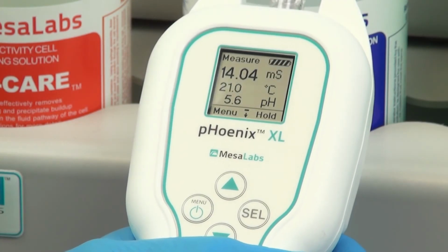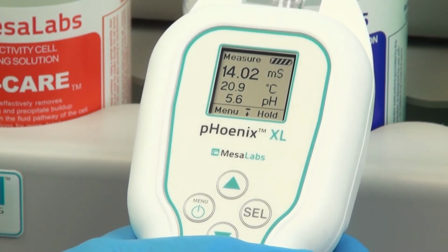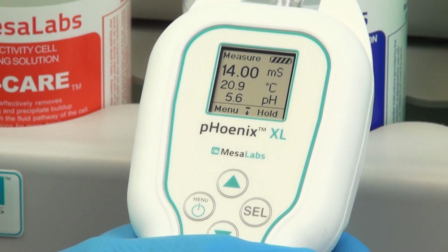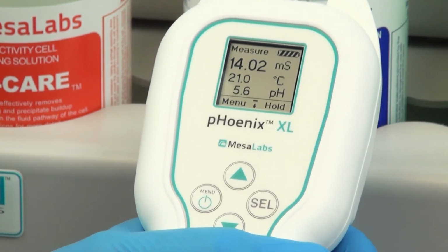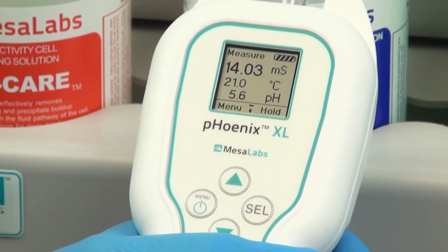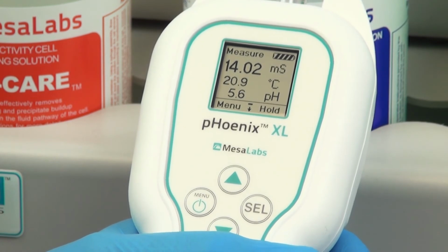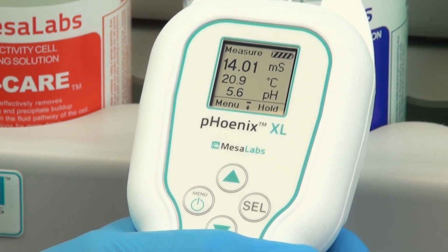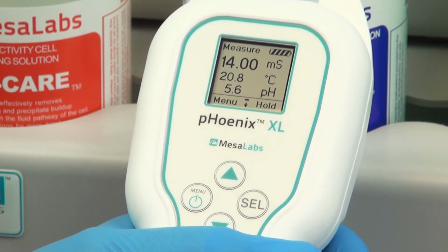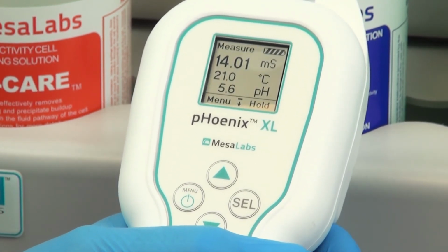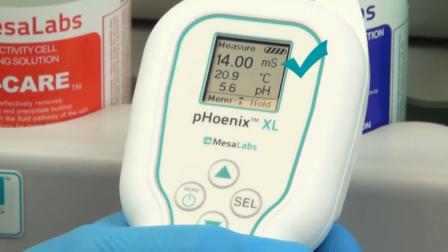Once you have saved your calibration, we recommend that you verify your meter against the same solution. Unlike the calibration, you will be looking for the exact same number for either pH or conductivity that you see on your calibration solution.